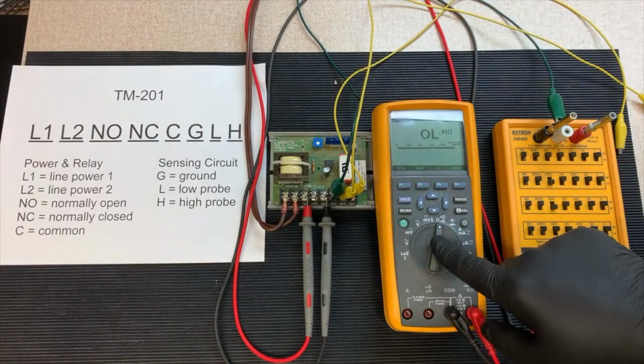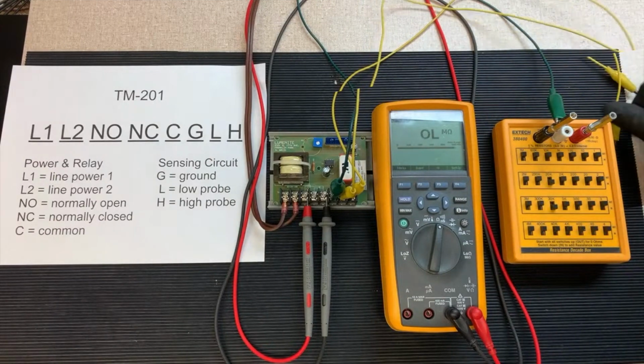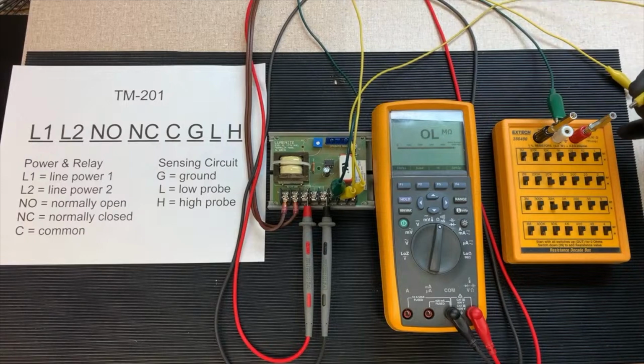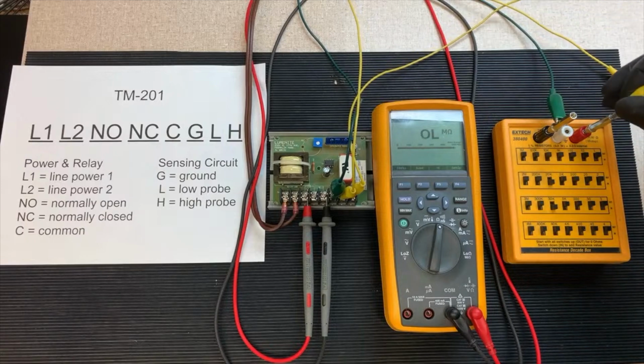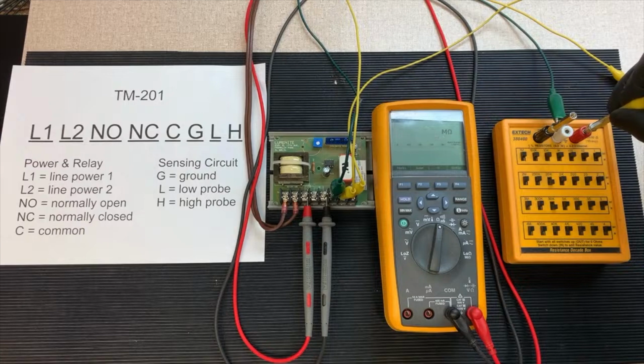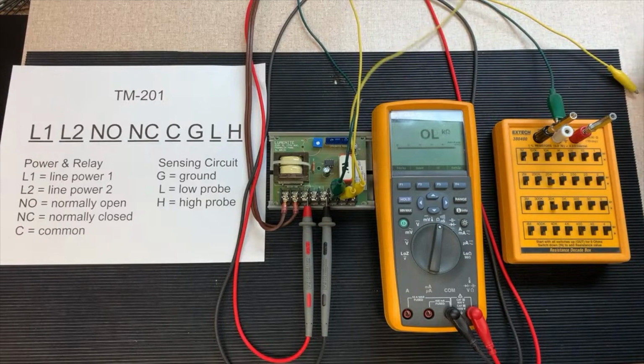We have open line here. So what we're going to do is just take our high terminal, high alligator clip, and we're going to touch it to the probe. So we have a good connection between probe and ground, and you hear the relay energize, and there we have good switch closure on the relay. We can also test it using the low probe.